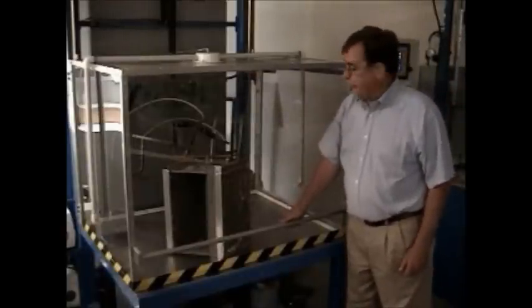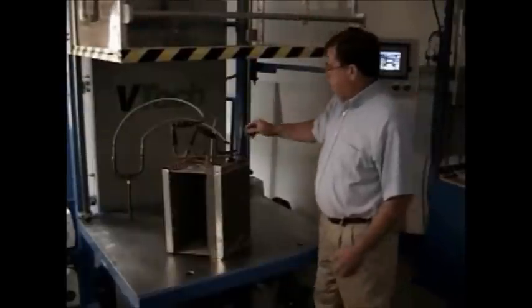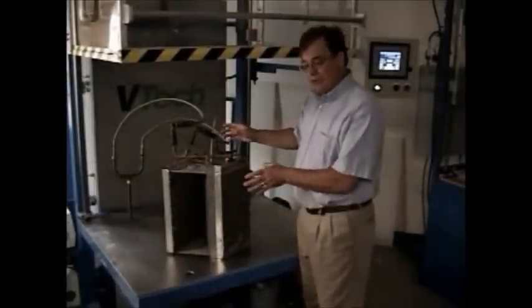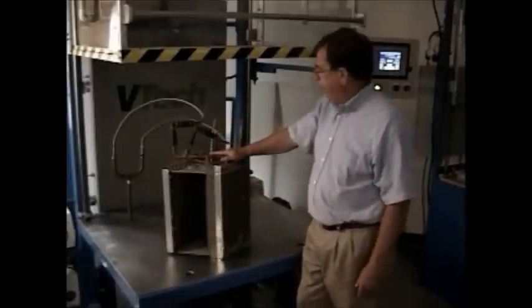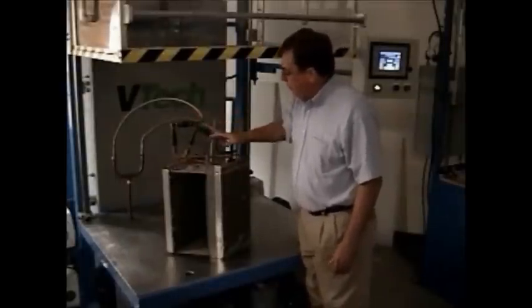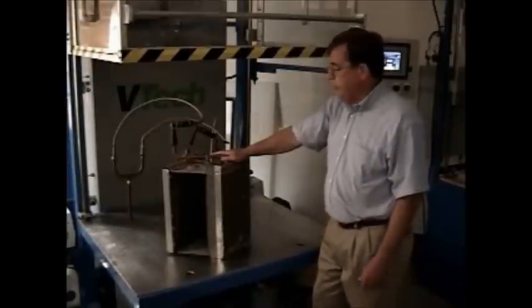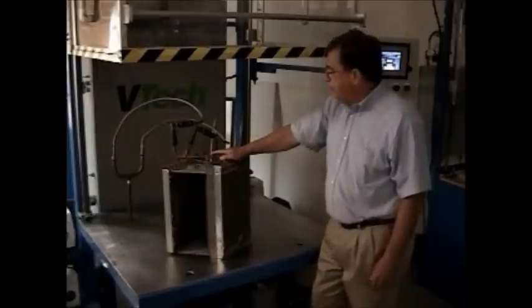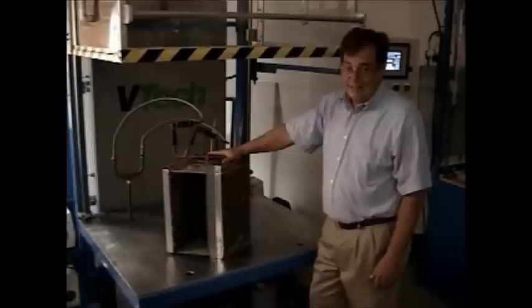The principle of operation is this. Units can still have the quick disconnect. For demonstration purposes, we're going to use this one coil and just use one side of the unit. In testing the plate coil that was sent to us — the heat exchanger — we found that it has leaks in the helium test. But to give you a good demonstration, we'll choose a unit that's leak-tight.